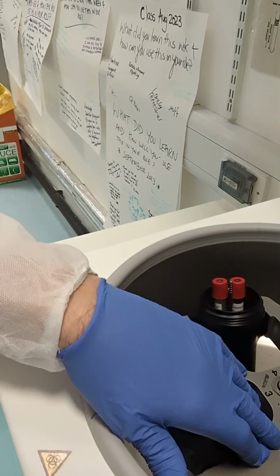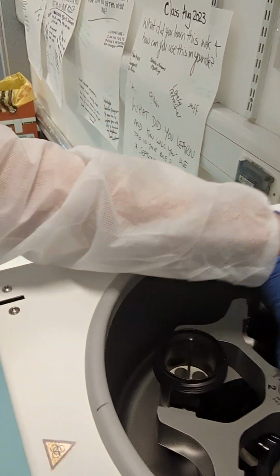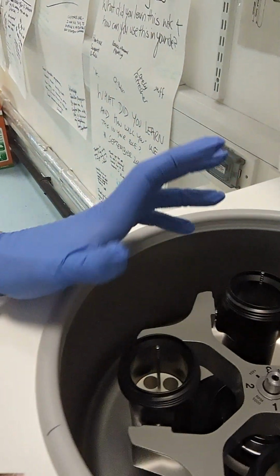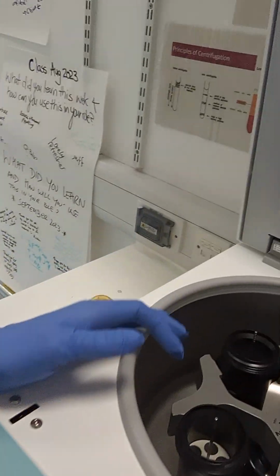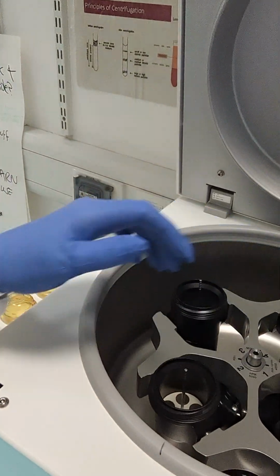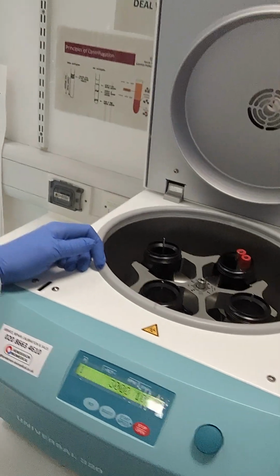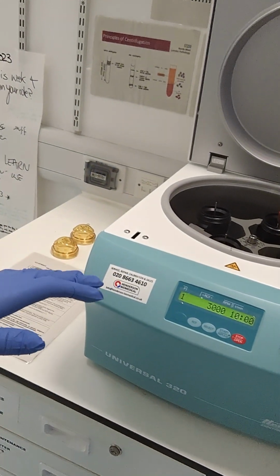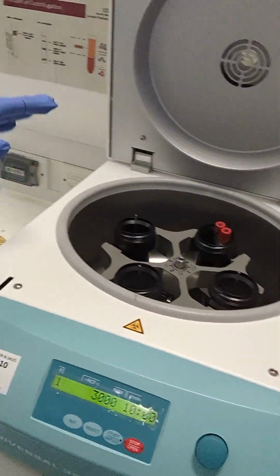It does generate a lot of force, so the rotor can over time become fatigued and generate cracks. If you're not happy, there are cracks or it does show signs of fatigue or it doesn't seem to be working properly, take the centrifuge out of use, report it to Henderson and report it to ourselves. Like I said, Henderson will come out once a year and they will check all these components for you and calibrate. And that is it. That is the daily checklist. If the centrifuge needs cleaning at any point, you can do that with surface disinfection using 70% alcohol. And we're going to go through that now.